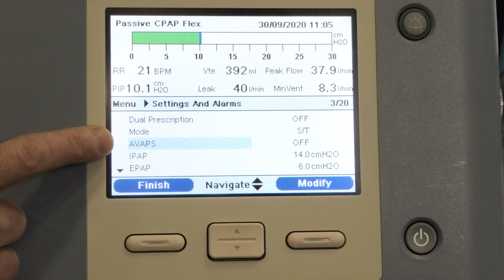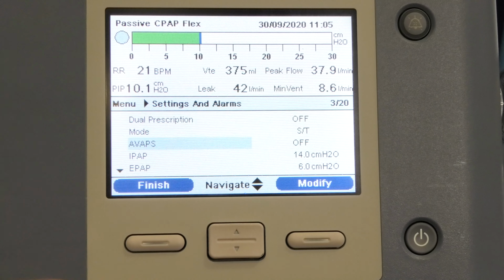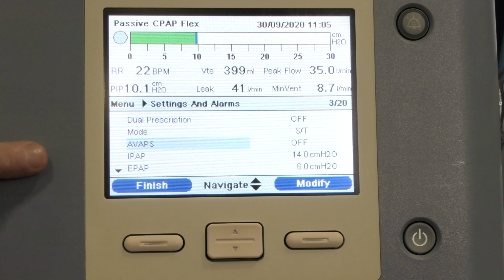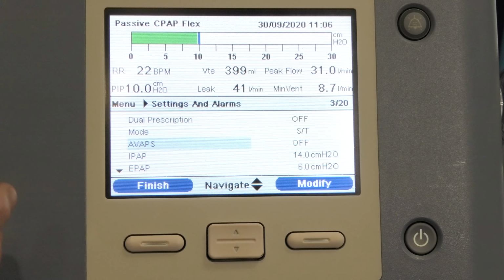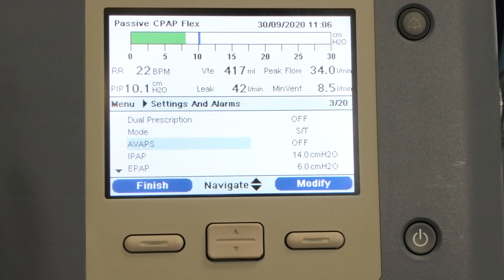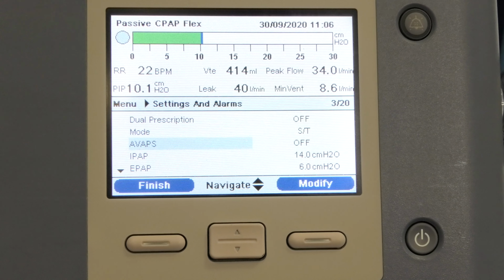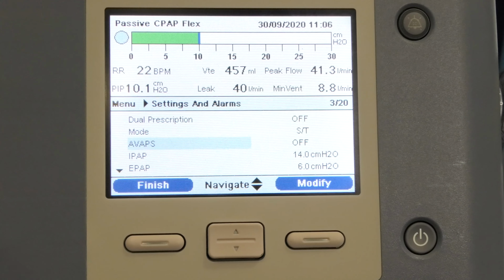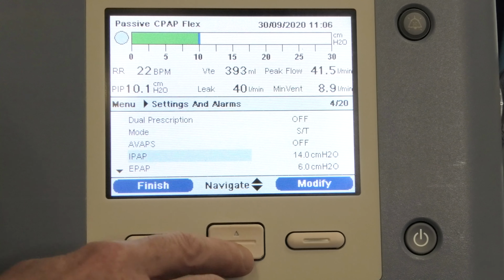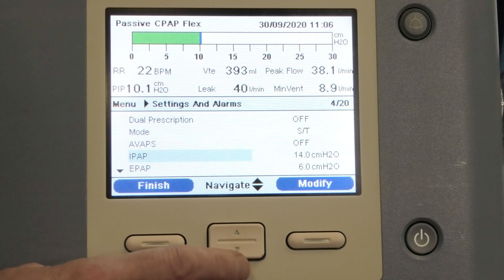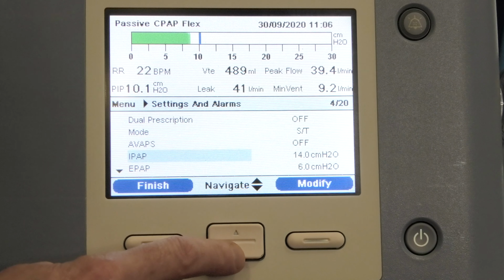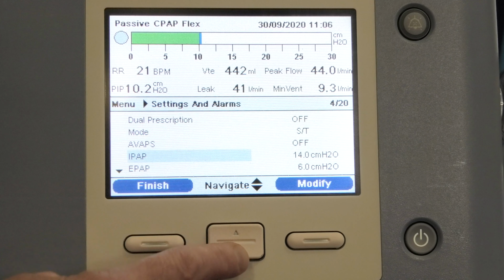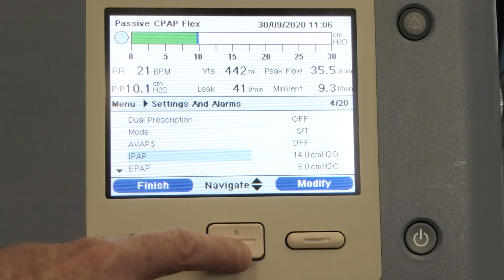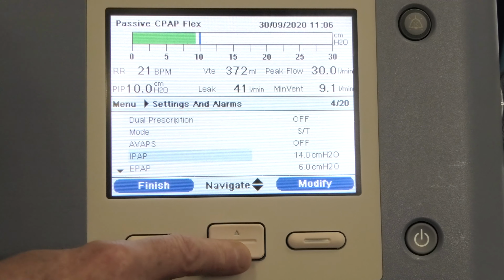AVAPS is a weaning mode, which we won't go into now. It's average volume assured pressure support, where you set a volume you want the ventilator to achieve and give it a range of IPAP. The machine decides how much IPAP to give the patient, so it titrates IPAP up and down. But in acutely unwell patients, we wouldn't use that. What we do need to set is our IPAP, and again, we'll be medically led, and the BTS guidelines are excellent in terms of guiding you what kind of pressures you need. We also have a BiPAP SOP, which is on the intranet, which you can access.